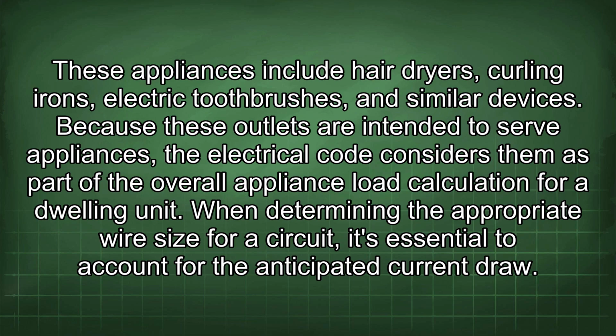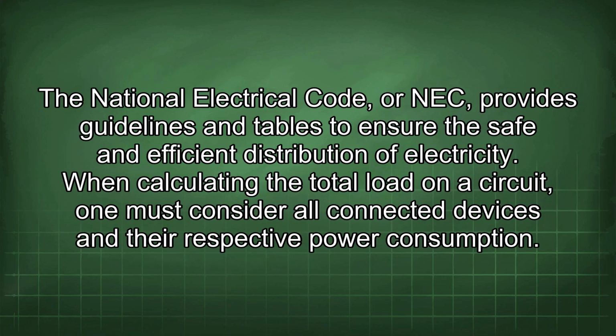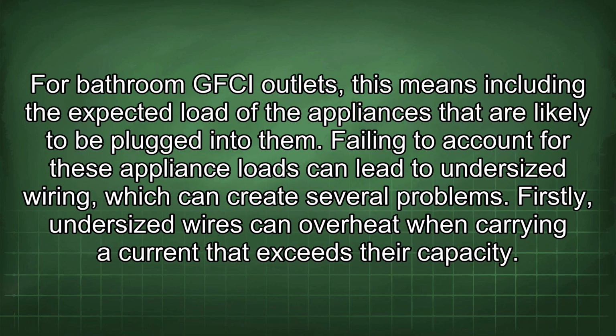When determining the appropriate wire size for a circuit, it's essential to account for the anticipated current draw. The National Electrical Code, or NEC, provides guidelines and tables to ensure the safe and efficient distribution of electricity. When calculating the total load on a circuit, one must consider all connected devices and their respective power consumption. For bathroom GFCI outlets, this means including the expected load of the appliances that are likely to be plugged into them. Failing to account for these appliance loads can lead to undersized wiring, which can create several problems.